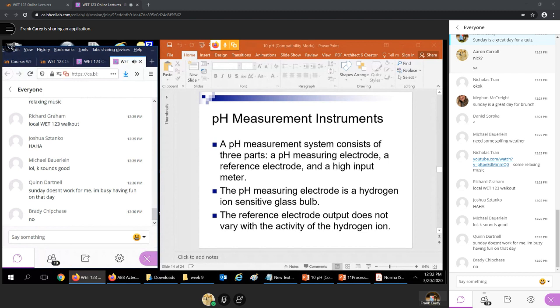So this reference electrode is sitting in a solution, and it generates a certain voltage constantly. And so the measuring electrode will either generate, based on the number of hydrogen or lack of hydrogen ions, a higher or a lower voltage than the reference electrode. So that's the basic premise behind how an electronic pH system works.